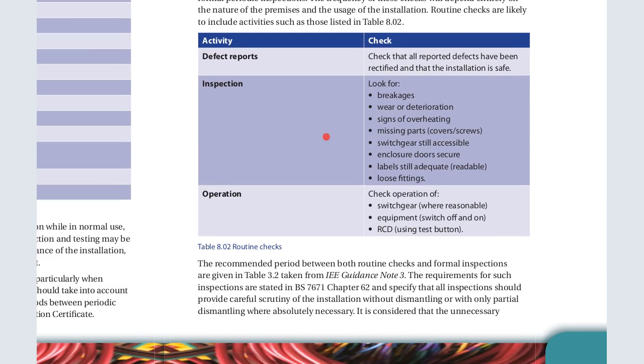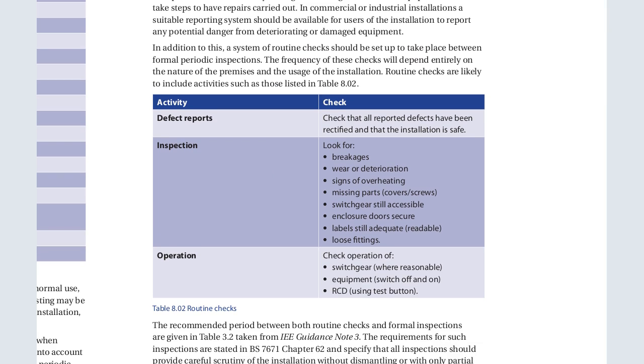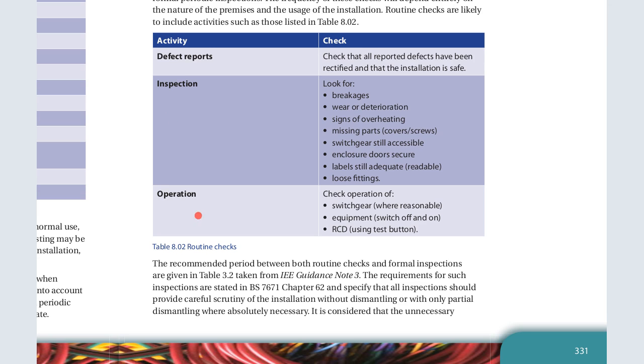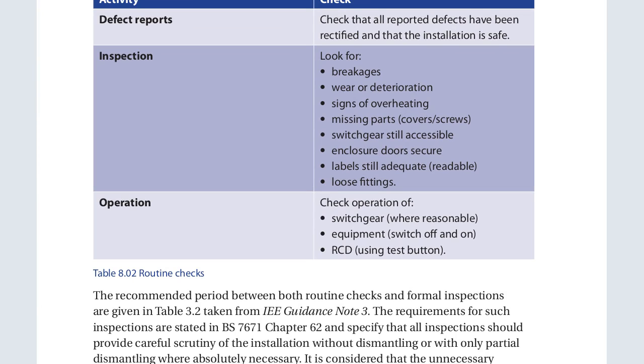So the activity and check. So the things that are checked. Now, if we have activity for defect reports, we check all the reported defects to see if they have been rectified, and also check if the installation is safe. Now, during inspection, what is checked? When inspecting, you look at breakages, wear or deterioration, signs of overheating, missing parts, that is the cover plates or the screws. We check that the switchgear is still accessible. We make sure that they are still accessible.